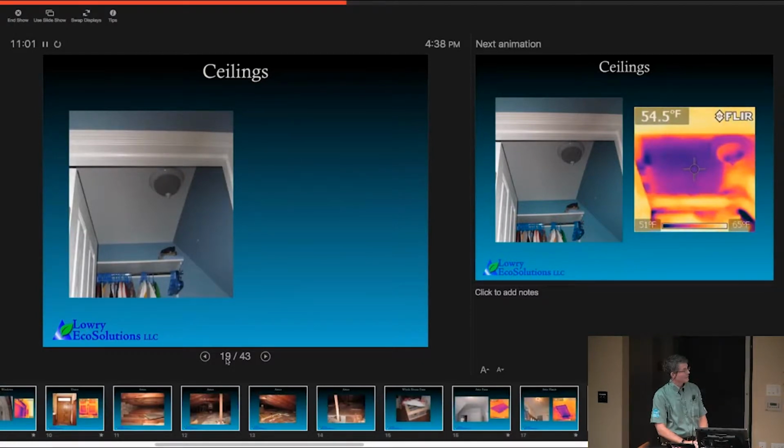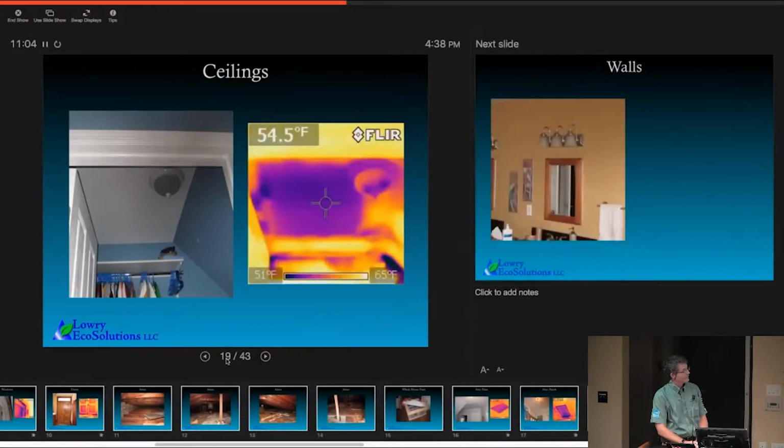Same young man's closet. Whoa. Nearly the entire closet is uninsulated. And this is a new house. But was that the attic above that? That was the attic above that. But you couldn't see the attic. You couldn't, in that case, because it was walled off and there was no hatch to access it. So we cut an 18-inch by 18-inch hole, I know I can fit through that for a fact. So, get up there, you add some insulation, you do some air sealing, it gives you a good opportunity to put in other wiring or whatever you might want to do, and then you patch up your little hole.